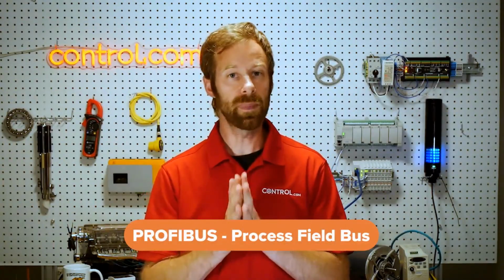I want to be careful that Profibus is not confused with Profinet. Profinet is an industrial Ethernet variation that's made for the process field industries. Profibus, on the other hand, was built again on an RS-485 system, multi-drop, which means a single line of twisted pair wire that has nodes or individual devices built into it. Profibus can connect to remote I/O nodes, but it also is installed in some process devices like temperature sensors and flow control sensors, so these are found in both the sensors and in the hubs themselves.